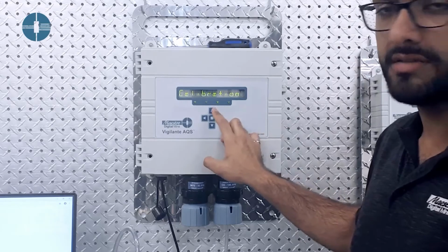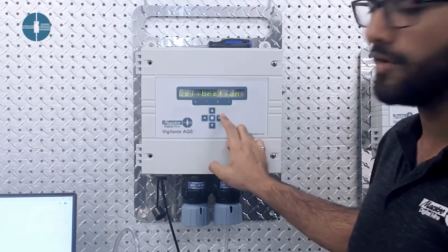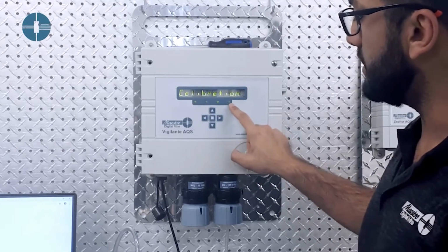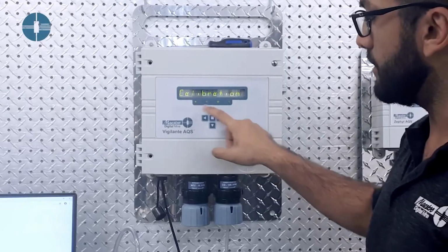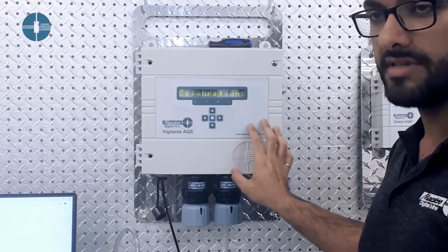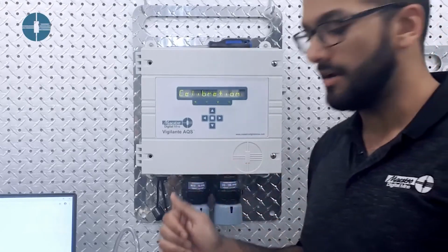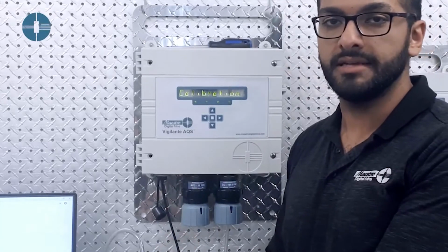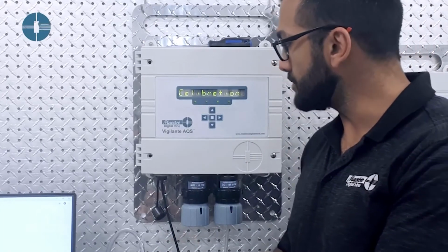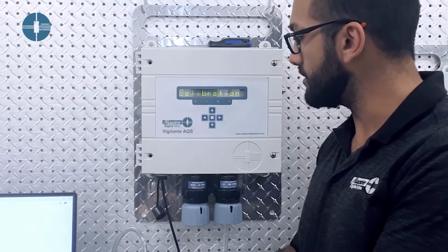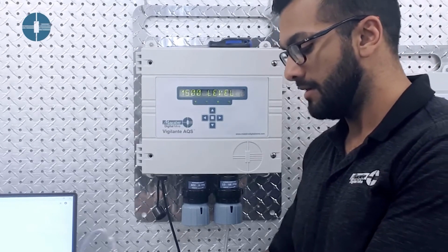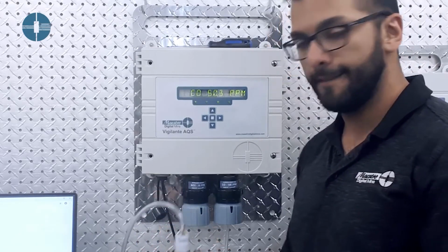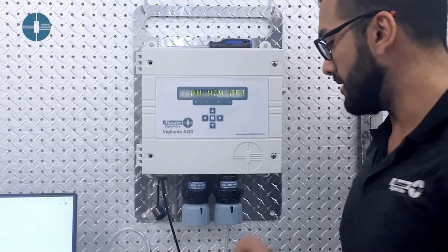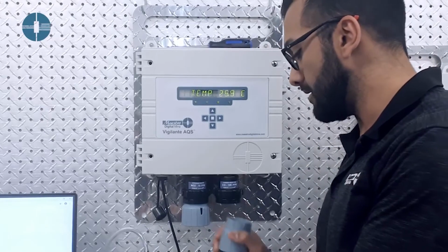One visual check to make sure that your sensor has successfully calibrated is the LED indicators over here. And if they're green, that means all the sensors that are connected on the Vigilante right now are all communicating as expected. So once the calibration is complete, we're going to turn off the span gas. And we're going to remove all the span equipment.